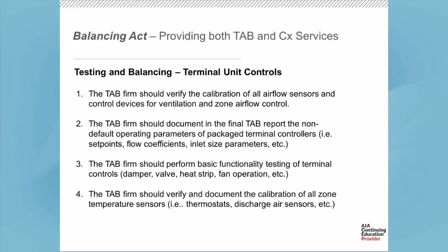And for that, they have to go through the controls to do that. They need to document in the final TAB report all of the non-default operating parameters of package controllers. If you're familiar at all with BAS controls and the way that terminal unit controllers operate, there's typically canned control sequences in these controllers. And you make slight changes from default values to achieve the intended sequence of operation. And those need to be noted somewhere. And we argue that the TAB firm needs to include that in their report as part of their verification of the terminal unit controls. They should also perform functionality verification and document the calibration of all the temperature sensors related to the terminal units.